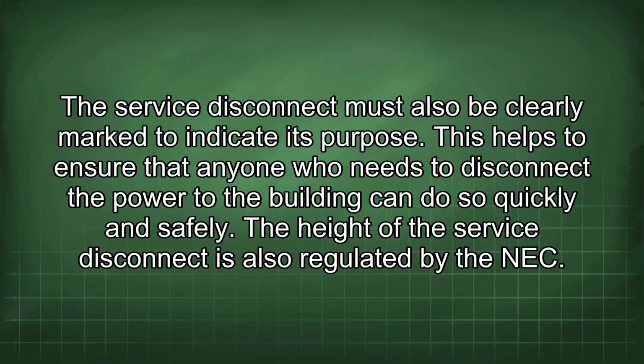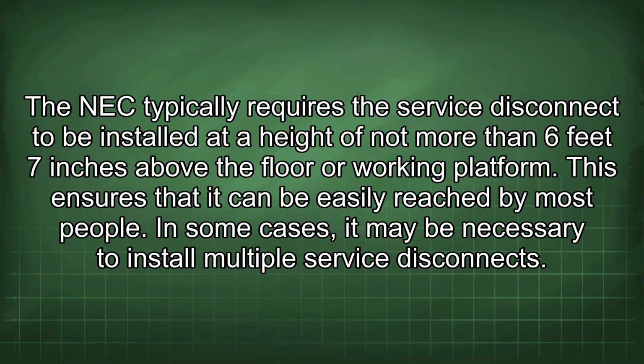The height of the service disconnect is also regulated by the NEC. The NEC typically requires the service disconnect to be installed at a height of not more than 6 feet 7 inches above the floor or working platform. This ensures that it can be easily reached by most people.